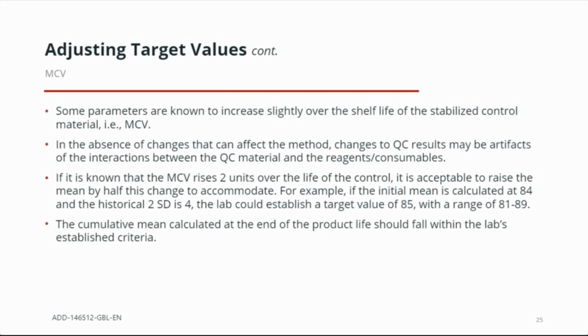For example, if our initial mean is calculated at 84 and the historical 2 standard deviation is 4 femtoliters, then the laboratory can establish a target value of 85 with a range of 81 to 89. This cumulative mean calculated at the end of the product life should fall within the laboratory's established criteria. CAP, CLSI, and international standards allow for means of a parameter that change over time to be adjusted. The key is to demonstrate this in the data set and to document the rationale. Again, this prevents unnecessary recalibrations for a measurand, which gives the laboratory back time, avoids waste, and adds value.